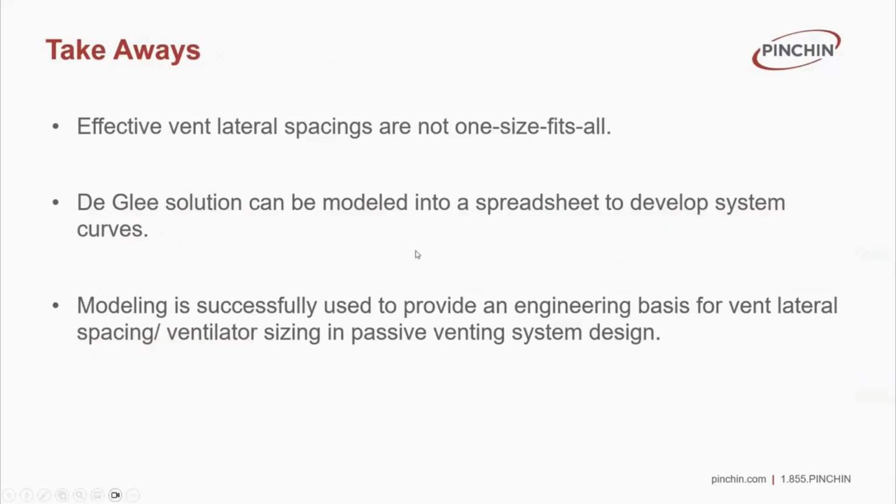Takeaways: effective ventilator spacing is not one size fits all. You can't just use 50 feet of spacing in every situation. The De Glee solution can be modeled in a spreadsheet to develop system curves, and modeling was successfully used to provide an engineering basis for ventilator spacing and ventilator sizing in this case.